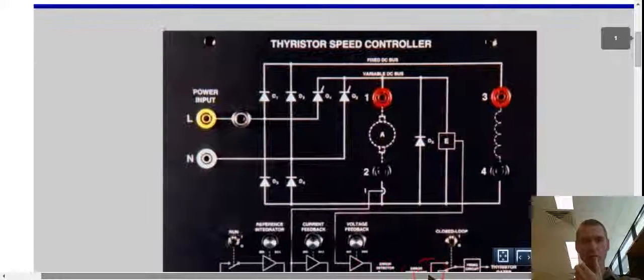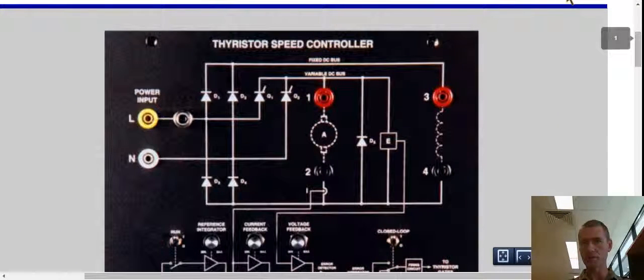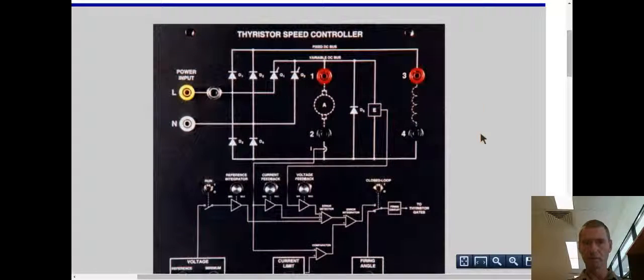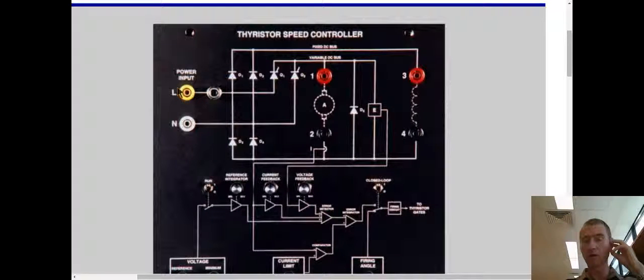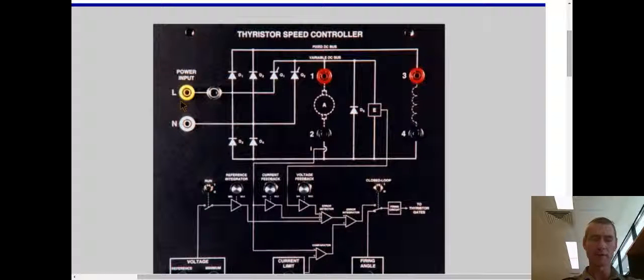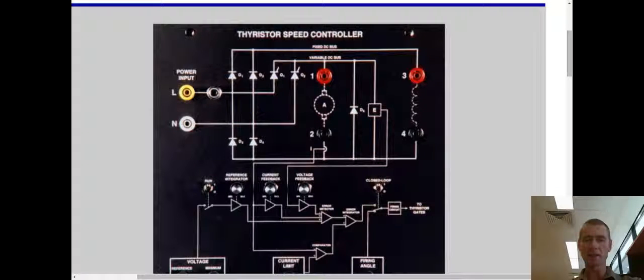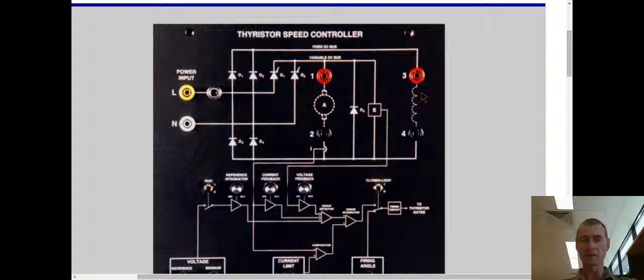Now, connection wise, we'll just zoom up here a bit. So you supply the power input with 240 volts AC. There's a little five amp circuit breaker here. This is a DC rectifier, which creates a DC bus that goes to the shunt winding on the DC motor.